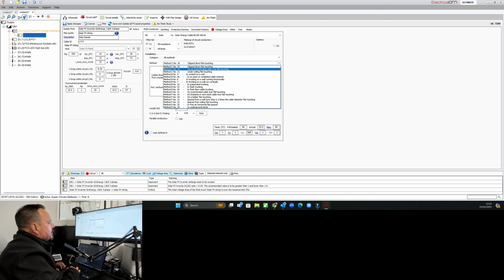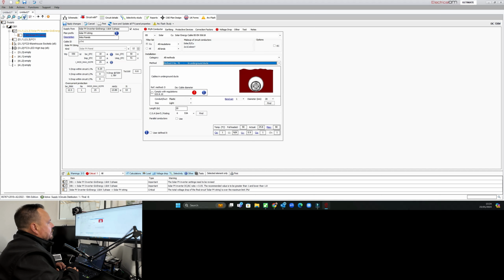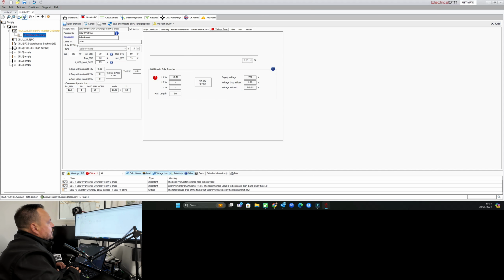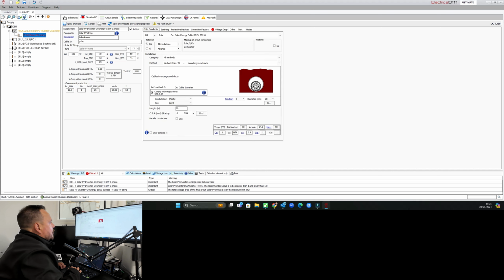No, let's use something we haven't used. What should we put them in? We'll put them in an underground duct, and we'll say we've complied with these regulations, just for something different as an installation method. So we can see that on there. And you see in the volt drop, we've got 13.49% on L1, and that's because we've got the one string on there. So it's really not reflected in the overall installation. We need to make sure we're getting the full spread across the entire system. So we'll keep going for the minute, and we'll look back at that in just a second. So you can see we've got our 6mm there. That's our first string done.